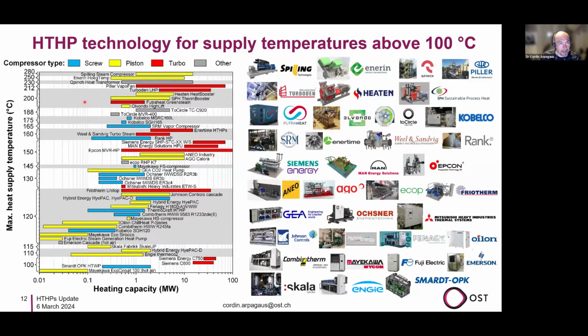In this Annex 58 we also included vapor recompression technology as an open heat pump cycle - meaning steam is compressed to higher pressure, achieving higher temperatures and pressures. This is not only looking at closed cycle heat pumps, where the cycle is limited by the thermodynamic properties of the refrigerants, by the critical temperature.